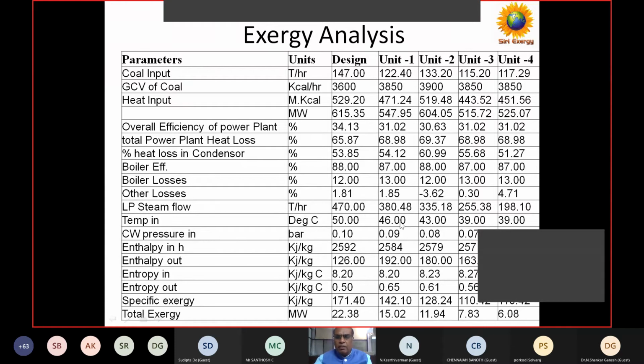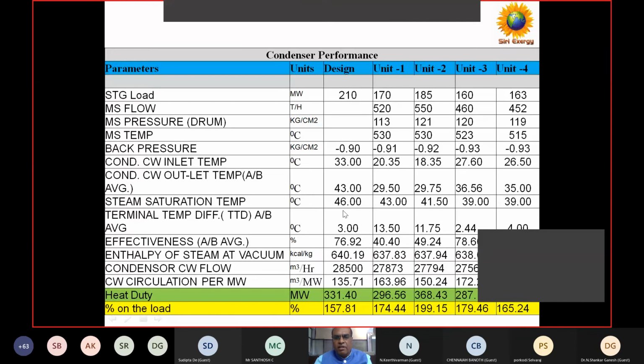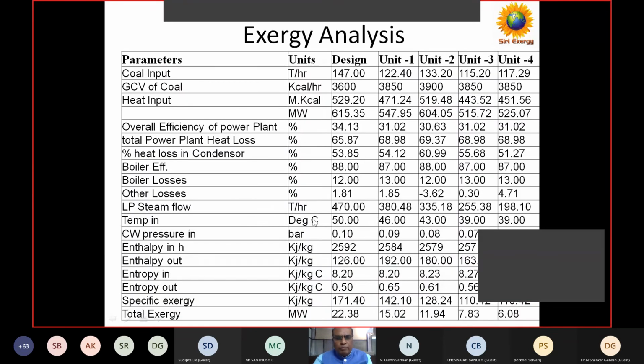This is your hot well temperature. When you are cooling through cooling water, it will come to the saturation temperature for that steam. So you will get 46 or 43 as the saturation temperature, and once it is out, we can get the cooling water outlet temperature. The cooling water temperature, as I showed in the earlier slide, because this is the north, is going even lower. We are getting outlet temperatures as low as 26, even 20 degrees, because of winter. So we analyzed the entropy in, entropy out, and also the exergy in, exergy out.